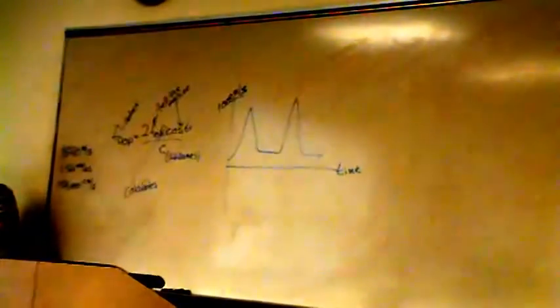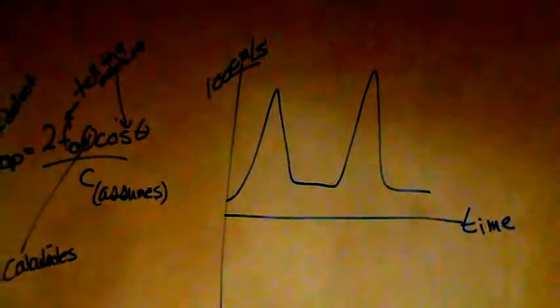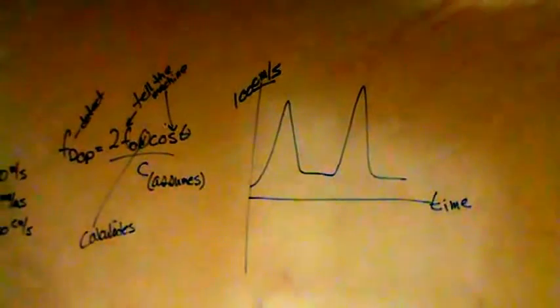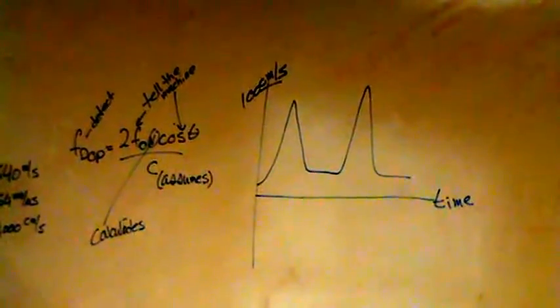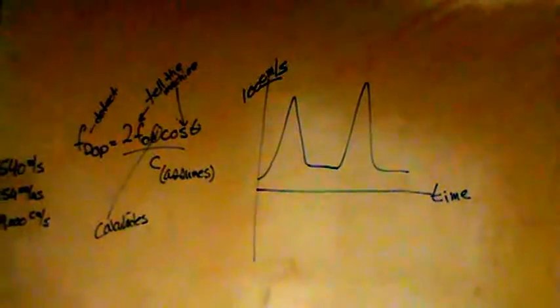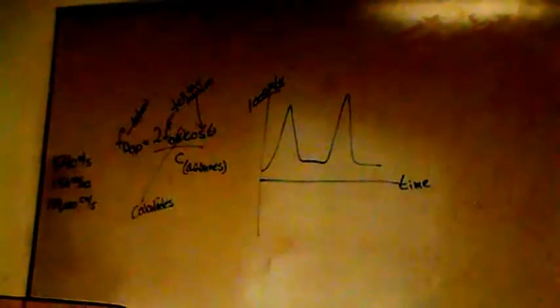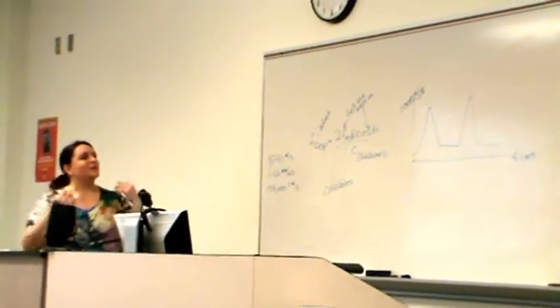If you're using good technique, using a transmit frequency, operating frequency, of 5 megahertz, and use a nice 60-degree angle in a carotid, 125 centimeters per second corresponds to about a 4 kilohertz frequency shift. When I first learned, I did CW of the carotid system, and it was all in frequency shifts, not velocities. So we talk about something having a 20 kilohertz frequency shift. That meant a really, really high velocity. Tidbit you didn't really need to know, but I felt the need to share it anyway. All right, so it calculates that.